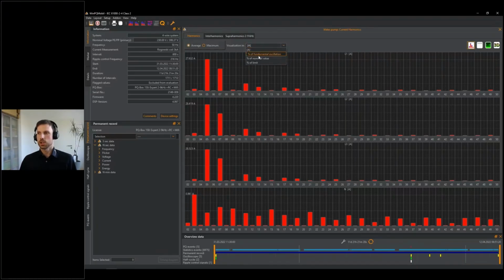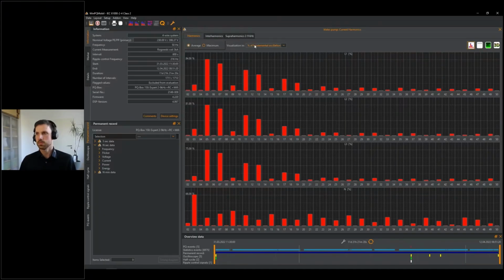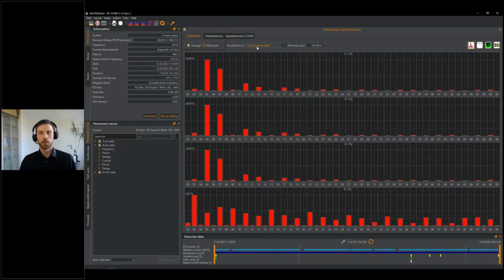If I change this to another display format, for example, in percent of the fundamental oscillation of the 50 Hertz network, the display changes to, for example, 84%, but still no limit value. I can also change this to a nominal value I can set individually, because some standards require a nominal value of the machine for the evaluation. I can change this in here, and if I type in 50, for example, now we are at 28%.